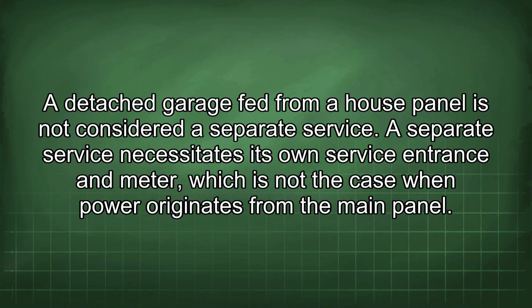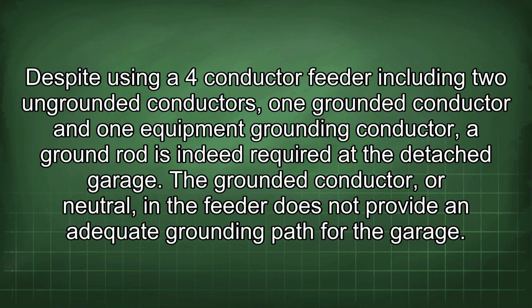A detached garage fed from a house panel is not considered a separate service. A separate service necessitates its own service entrance and meter, which is not the case when power originates from the main panel. Despite using a 4-conductor feeder including 2 ungrounded conductors, 1 grounded conductor and 1 equipment grounding conductor, a ground rod is indeed required at the detached garage.